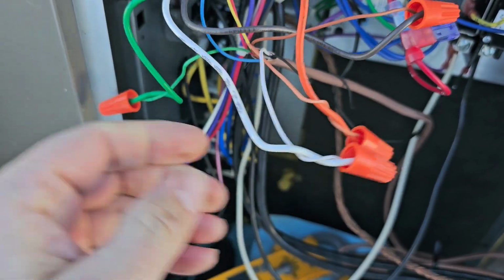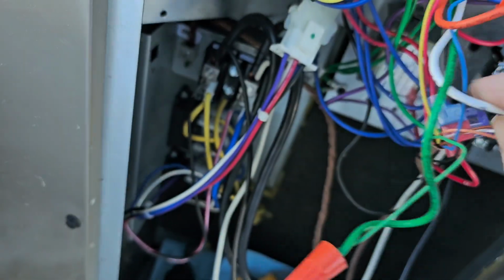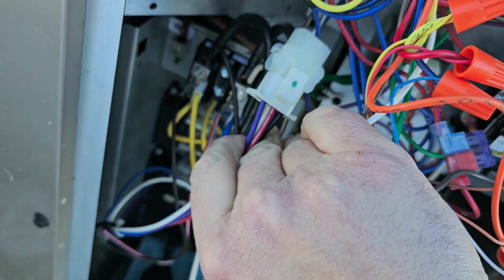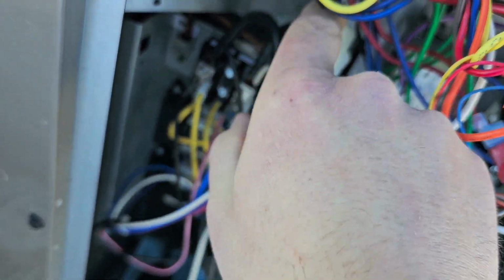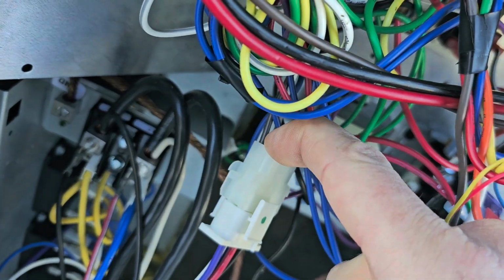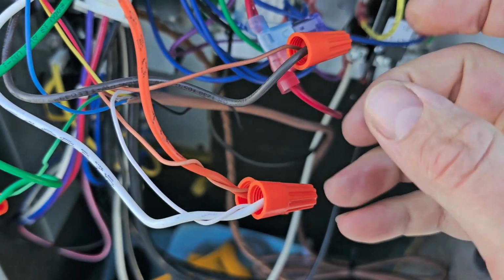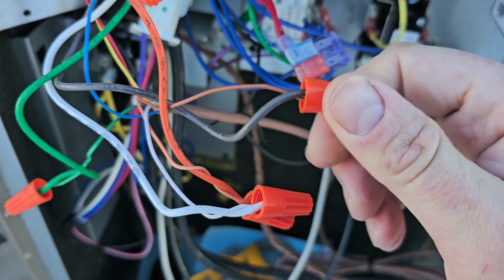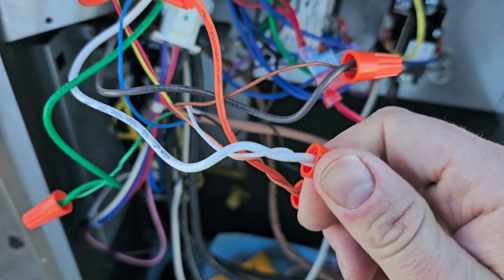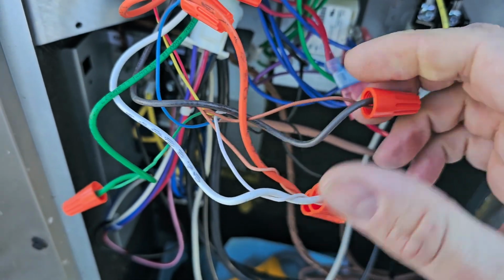Here's our white wire that goes to another white wire that goes to a plug. See that? And there's a brown wire, right? In that plug, white and brown. The brown went to our emergency heat. The white goes to auxiliary. So this brown wire should be going to one of these relays down here.